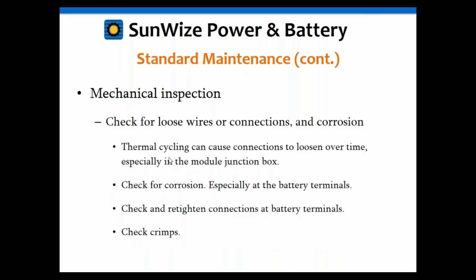Okay, just again, highlighting some things I said before, you're looking for loose wires or connections and corrosion. Thermal cycling can cause those things to happen. Corrosion, I know I was just showing you one on the outside, but again, corrosion around battery terminals is also very common. If the batteries do gas at all, the battery gas can be corrosive, so you'll find that a lot of the battery terminals are ones that also corrode. So again, check those.